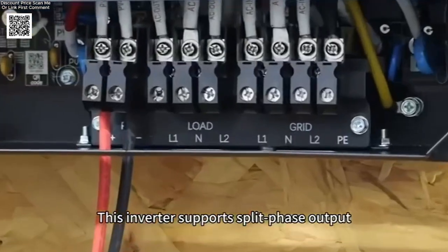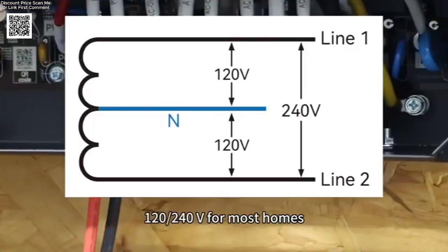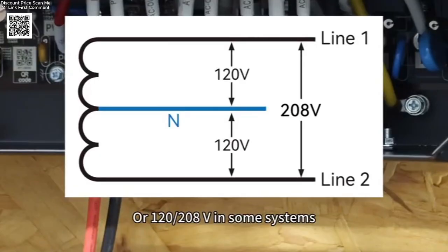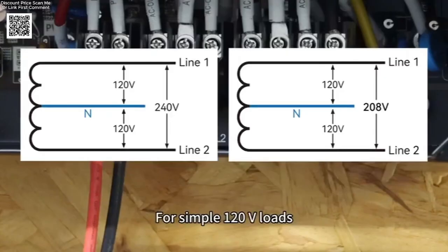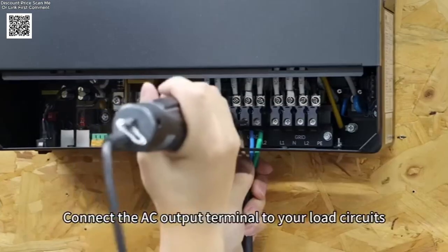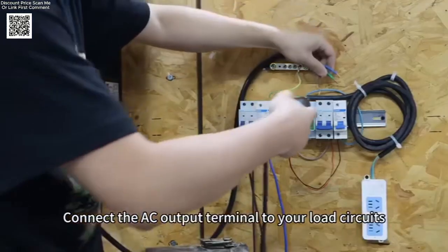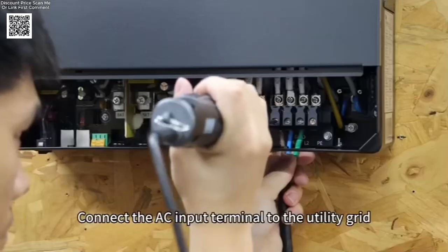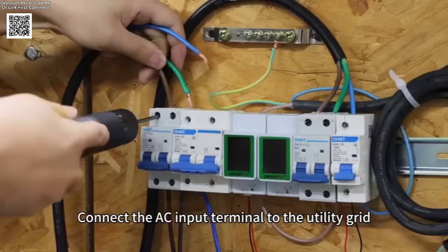This inverter supports split-phase output, 120/240 volts for most homes, or 120/208 volts in some systems. For simple 120 volt loads, use line 1 to neutral or line 2 to neutral. Connect the AC output terminal to your load circuit. Connect the AC input terminal to the utility grid.